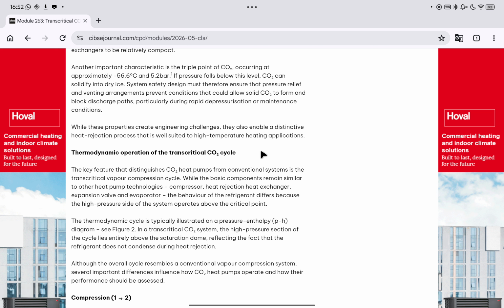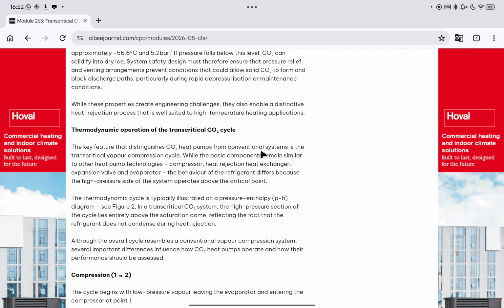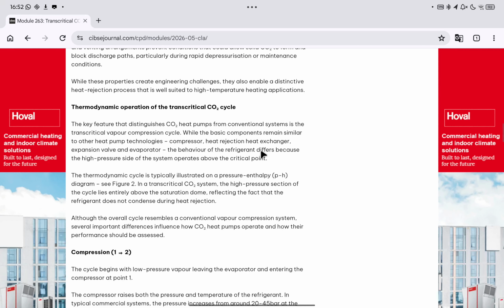See Figure 2. In a transcritical CO2 system, the high-pressure section of the cycle lies entirely above the saturation dome, reflecting the fact that the refrigerant does not condense during heat rejection. Although the overall cycle resembles a conventional vapor compression system, several important differences influence how CO2 heat pumps operate and how their performance should be assessed.